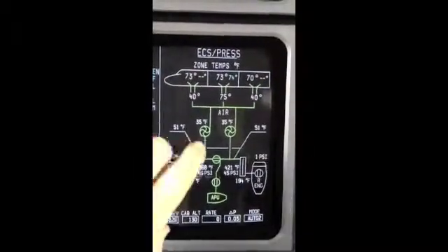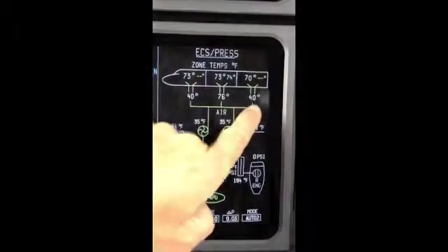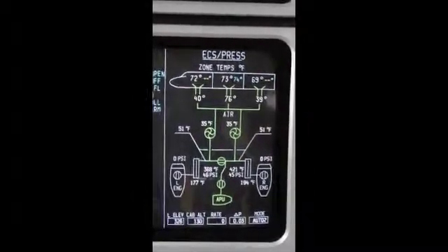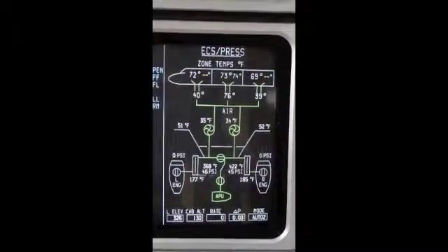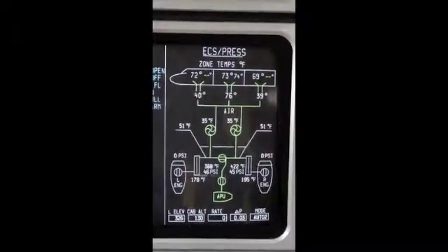What we're doing is comparing essentially these two temperatures right here — the 40 and the 40. I've turned the knobs all the way to the cold position, so the trim air valves are in the full closed position. Now it takes bleed air to get the trim air valve to the open position.